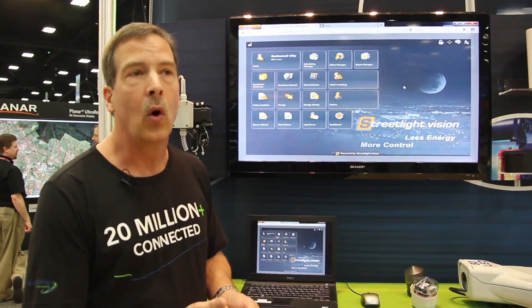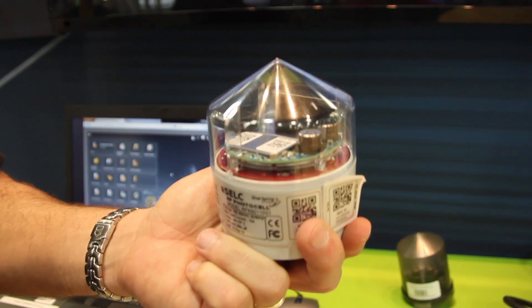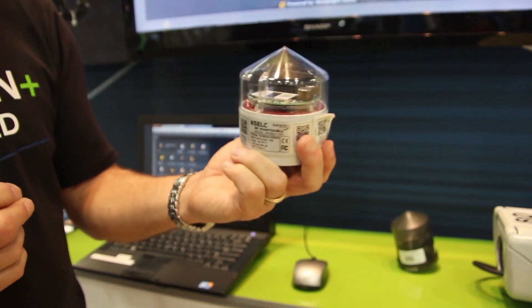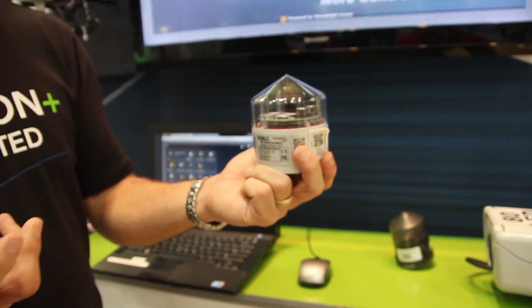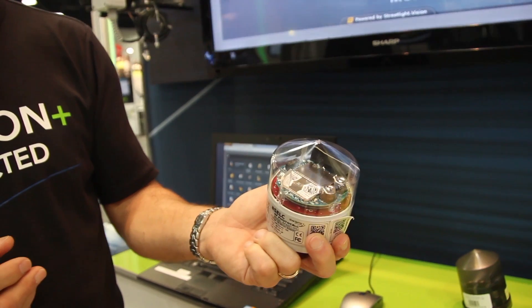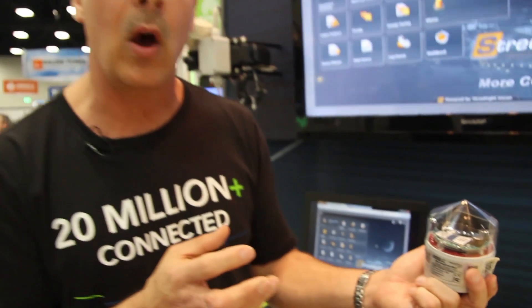The streetlight could be on during the day, or it could be failing to come on at night. This is a Silver Spring Gen 4 module, and it has the ability to communicate with the entire Silver Spring mesh network. It has a couple of advantages: it becomes a relay point to strengthen the mesh of the existing Silver Spring network. It also has metering capabilities, so the utility has the opportunity to meter and bill on a per-light basis. Many utilities will offer a flat rate fee for a number of streetlights, but if the business case demands, they can use the metrology on the streetlight itself and bill for actual usage.